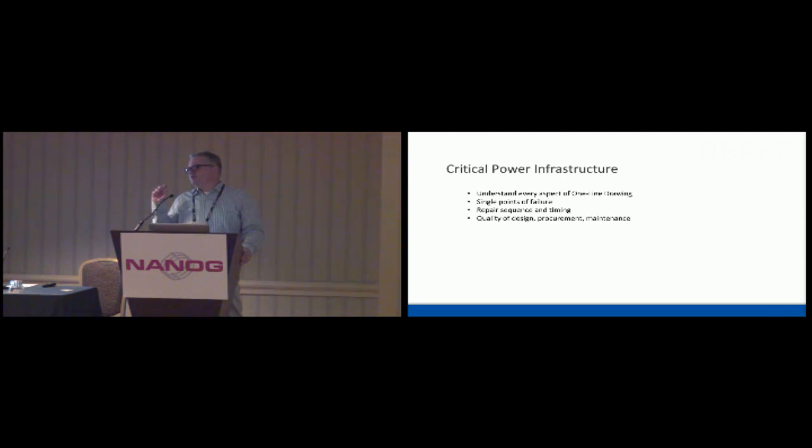And so that you can understand in different failure scenarios, utility failure, UPS failure, generator failure to start, what the implications of each of those things are, and be able to translate that into your risk profile and how well you need to deal with it. You need to understand, when you're looking at that one-line diagram, what any single points of failure are. And just as important as single points of failure, what the repair sequence and timing is behind that.